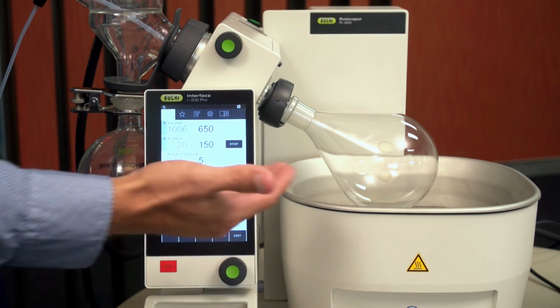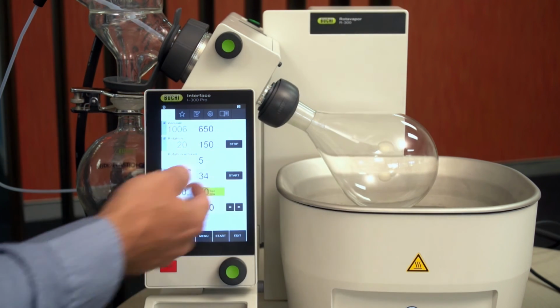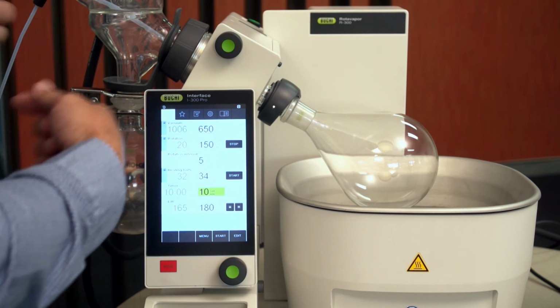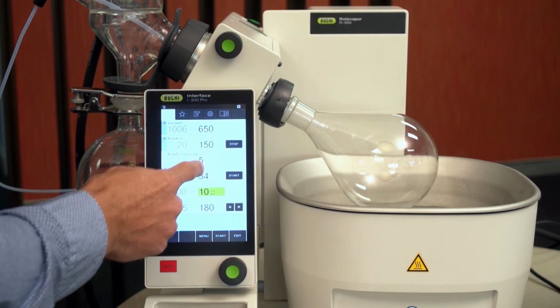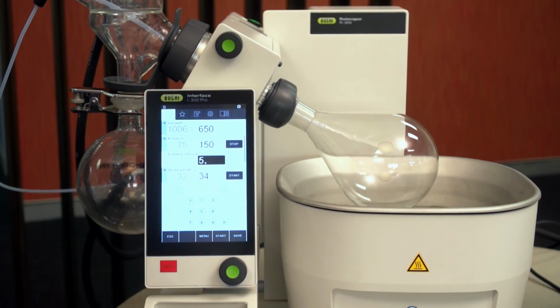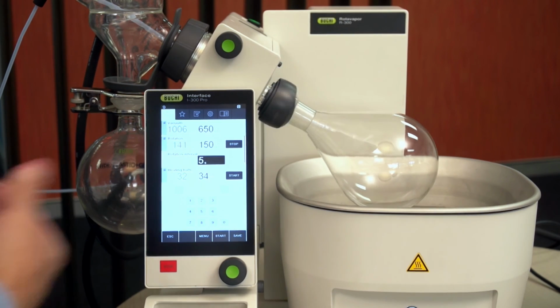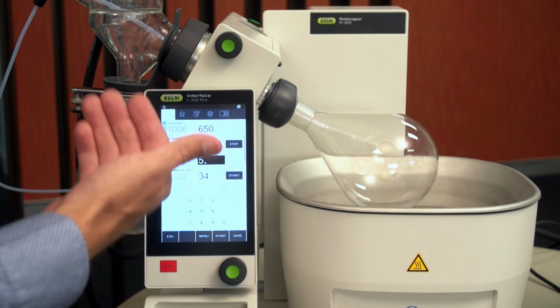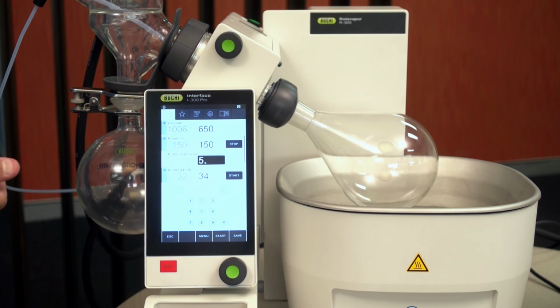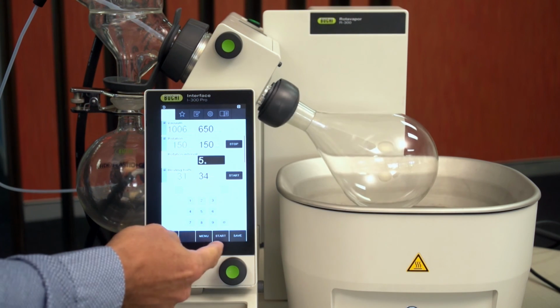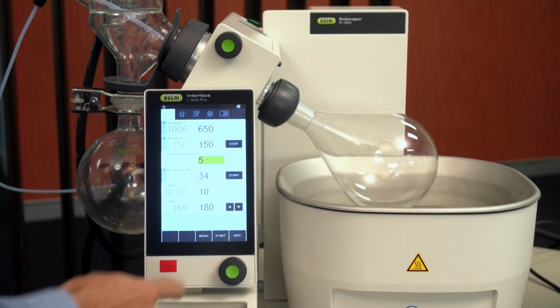We can set a lift for raising or lowering the height of our bath. For this example, I've raised it just slightly out of the bath so we can have a look at the anti-clockwise and the clockwise directional change. We can set our interval for 5 seconds or as long as you would like it. For this example, I'll set it at 5 so it's easy to see. I've set the vacuum at 650 millibar so the pump can pull down very quickly to try and keep this demonstration short. We hit save, I hit start.